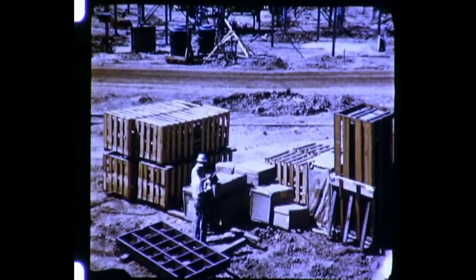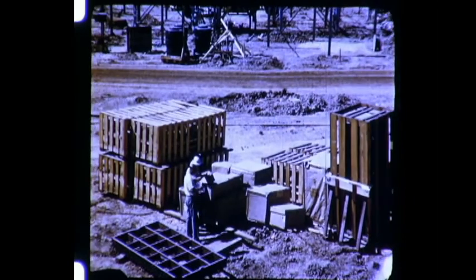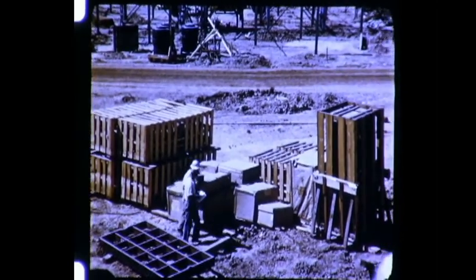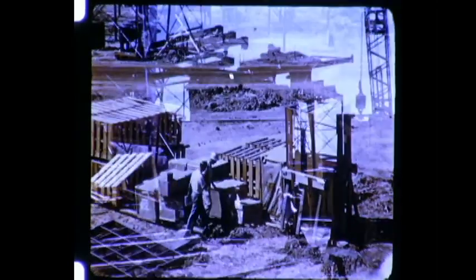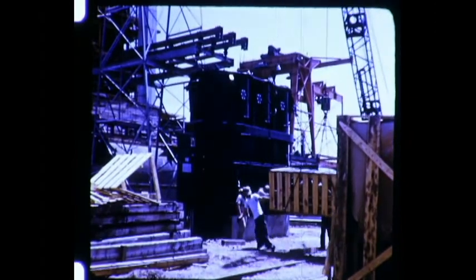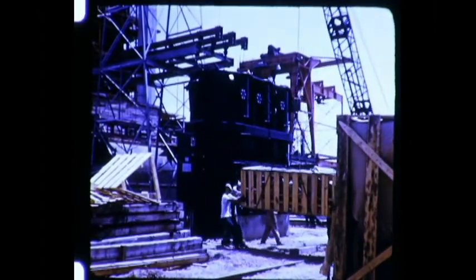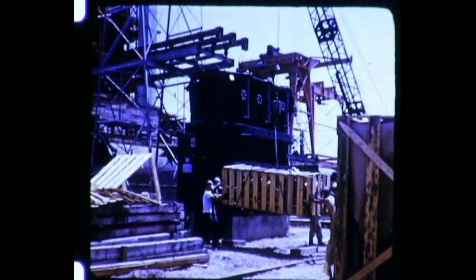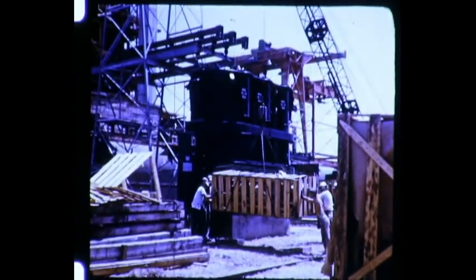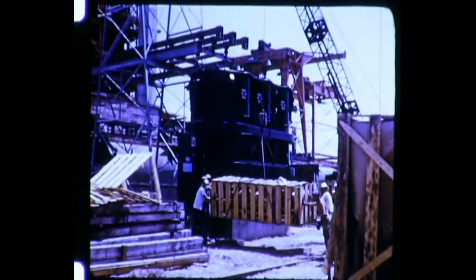This starts with a check to determine that all auxiliary equipment is on hand. A packing list shipped in one of the crates helps locate the parts. Following this check, the first of 6 unit coolers that circulate and cool the oil is lifted alongside the transformer and uncrated.